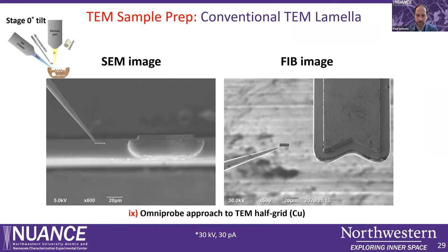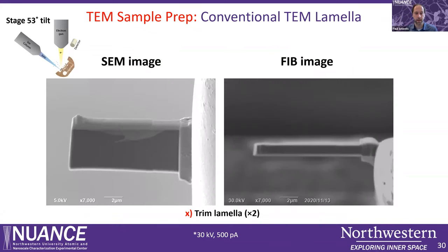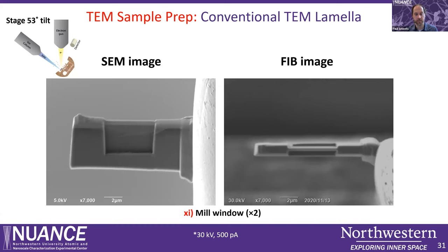I like to mount it on the side of a post as a flag. We use the GIS system to deposit a little bit of platinum to adhere the sample at lower currents. Then we tilt the sample perpendicular to the ion beam — 53 degrees for the 4700 system — and trim the lamella at milder currents initially. We then mill out a specific window. For this, you need to know how deep your gallium beam penetrates into the sample, which requires knowledge of your sample and some experimental practice.